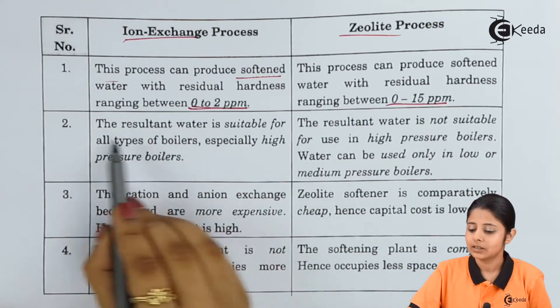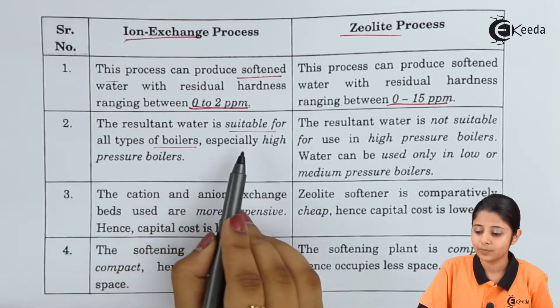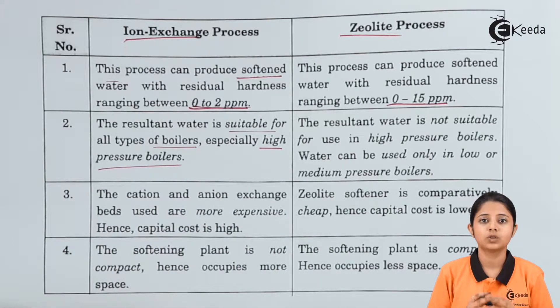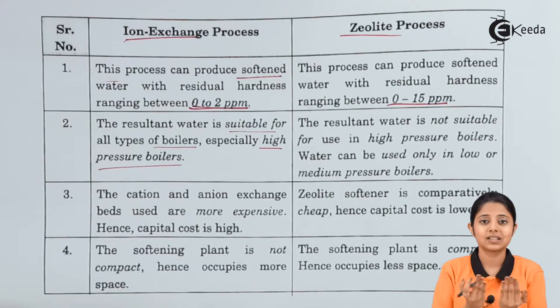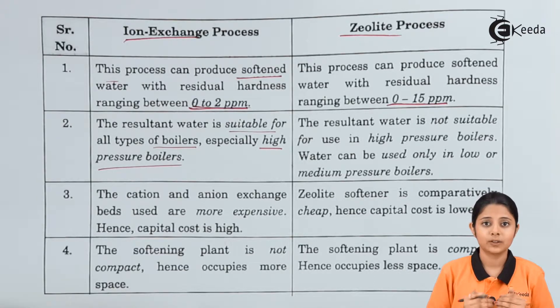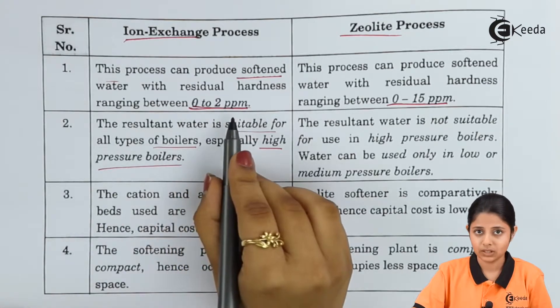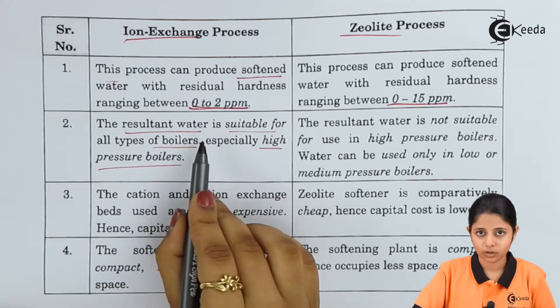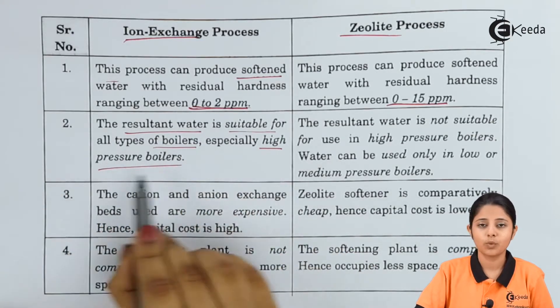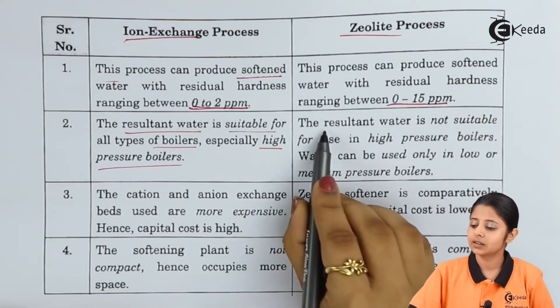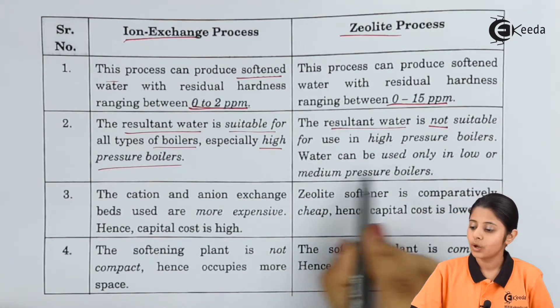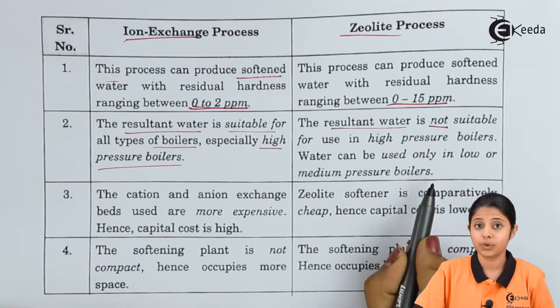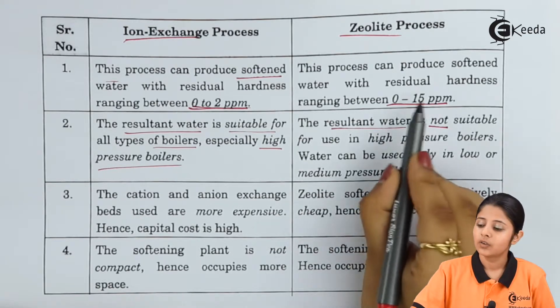The resultant water from the ion exchange process is suitable for all types of boilers, especially high pressure boilers. Boilers are machines that boil water, and impurities can get stuck to their walls. Since the softened water from ion exchange has only 0 to 2 ppm of impurities, it can be used in any kind of boiler. For the zeolite process, the resultant water is not suitable for high pressure boilers and can only be used in low or medium pressure boilers due to its 0 to 15 ppm of impurities.